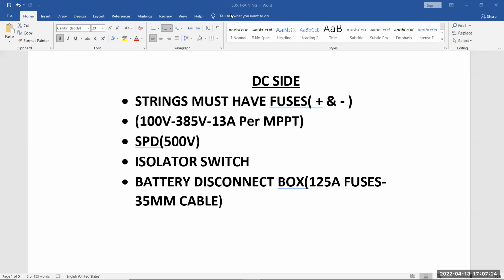What size of cable will you use from inverters back to main DBs for 2 and 3 inverters in single phase parallel? That's going to depend. It depends if you have 2 of these inverters. I will go 4 mil should be fine for 2 of them, but I'll always like to go a size bigger. So I'll recommend 6 mil for that, because 6 mil cable can run up to 41, 42 amps.